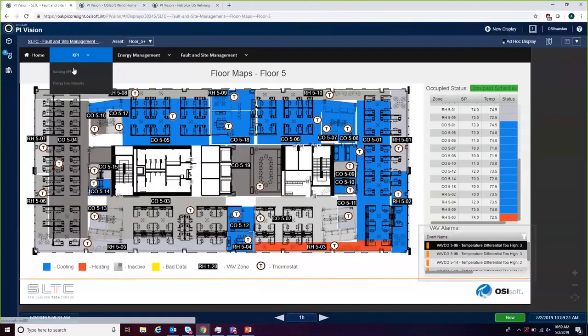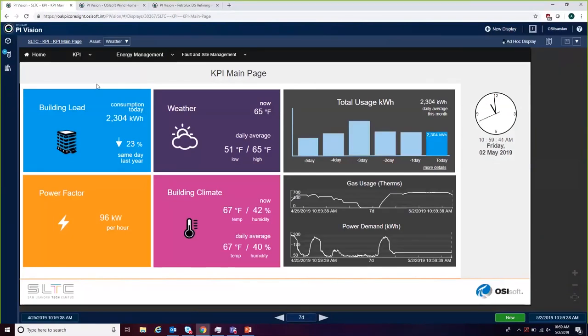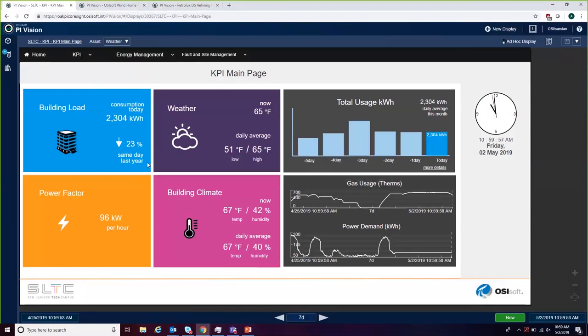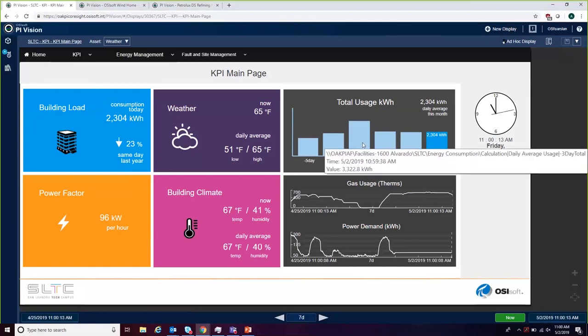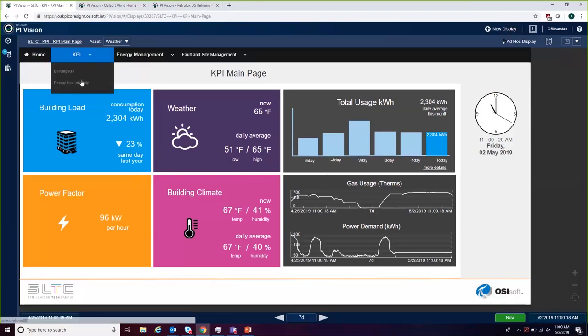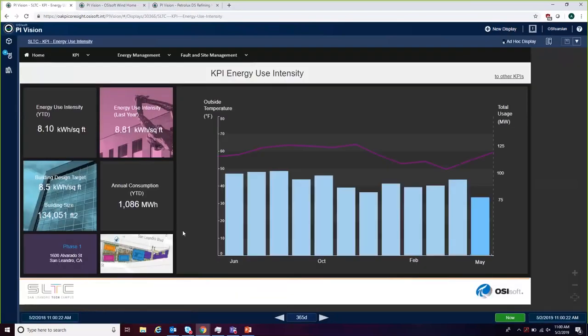I can take a look at certain building KPIs — useful for any building in terms of energy consumption. For today, I'm consuming 2.3 kilowatt hours, and analytics tell me this is down 23% from last year, which is good. I also have a general weather overview because that affects building energy usage, plus power factor and kilowatt usage on a daily basis for the last five days. I can look at gas and demand, intensity, and which parts of the building are using more or less energy.